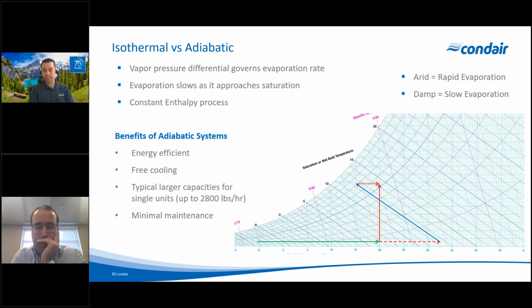With an adiabatic process, where we atomize or evaporate water into the air, it's effectively a constant enthalpy process, but for back-of-the-napkin calculations we can assume it's a constant wet bulb process—that's the blue line going diagonally. While we're increasing humidity, we're also dropping the temperature. That's an important fact to keep in mind when comparing adiabatic systems to isothermal ones.